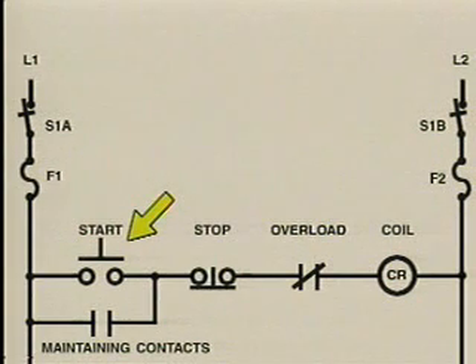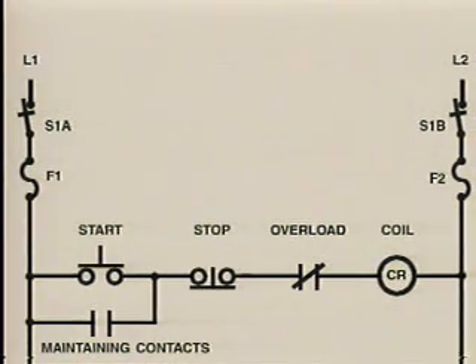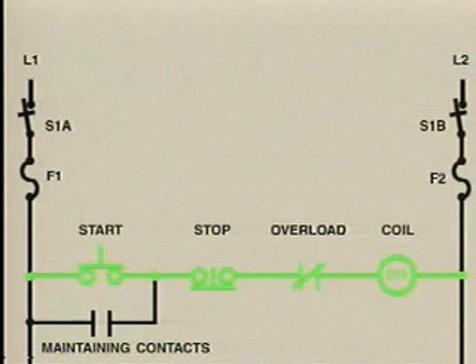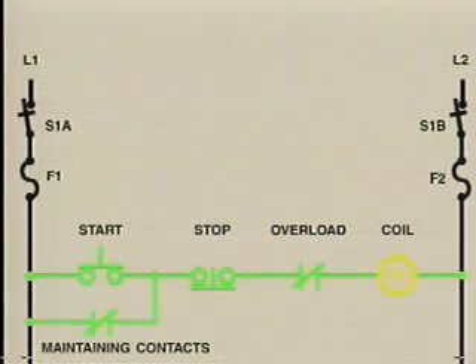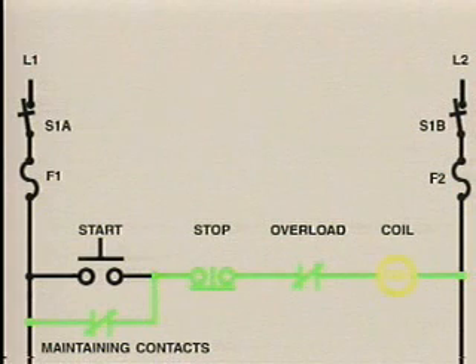When the start switch is pressed, its contacts close. This completes a path for current to flow through the start switch, the stop switch, the overload contacts, and the coil. The coil becomes energized when current flows through it. This causes the maintaining contacts to close. When the start switch is released, its contacts open. However, because the maintaining contacts are now closed, current can still flow through the coil, keeping it energized.